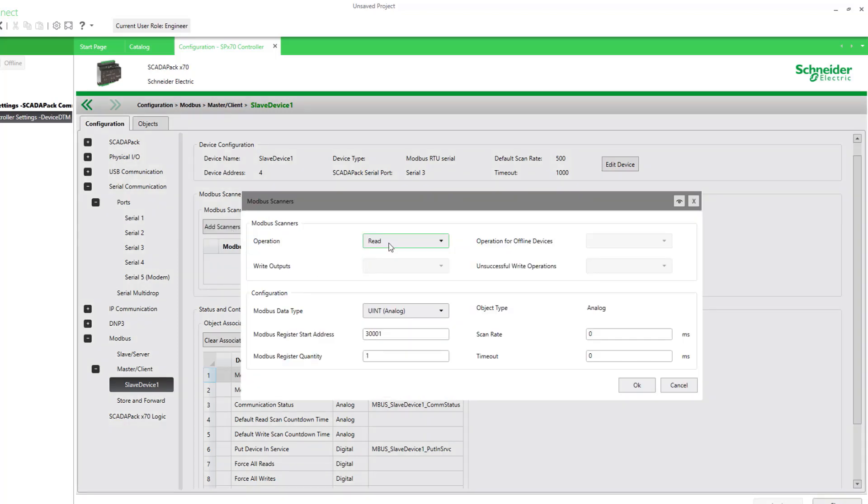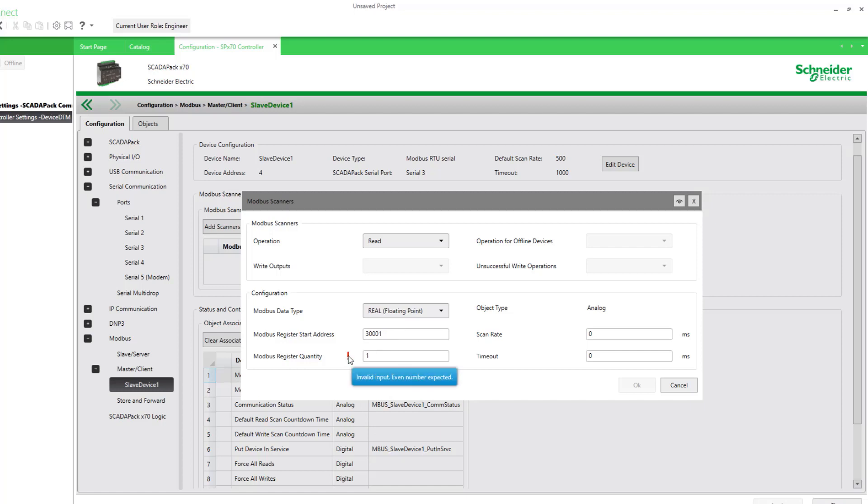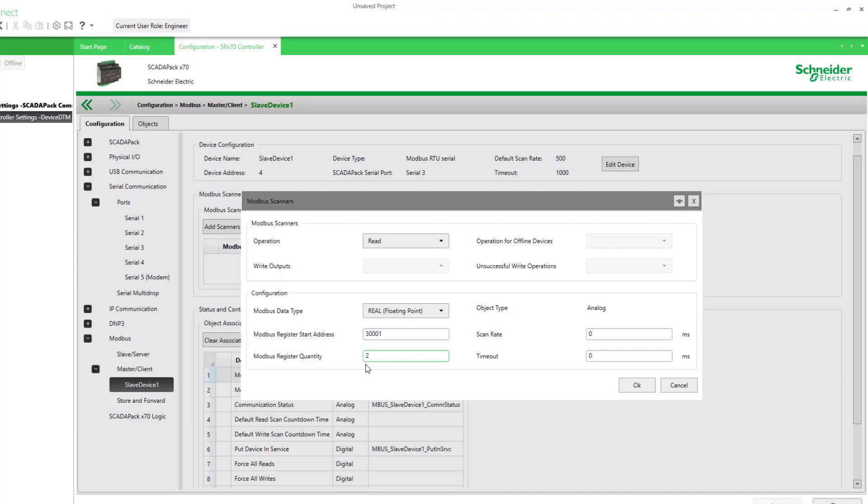Our pressure and our temperature will be a read operation. The pressure is real, so I'll select a real value. And it begins at 30,001. And this is a good reminder here. We're pulling 32-bit real registers, so there are always two registers per real point. So it's just reminding you we need an even number. So for our one pressure, we'll have two registers there.